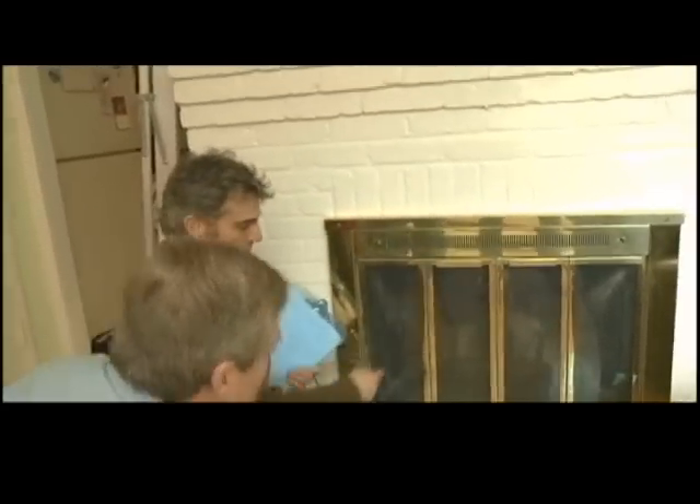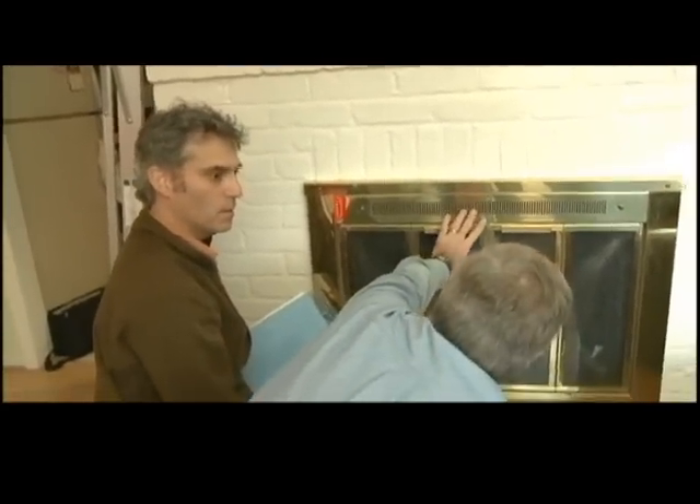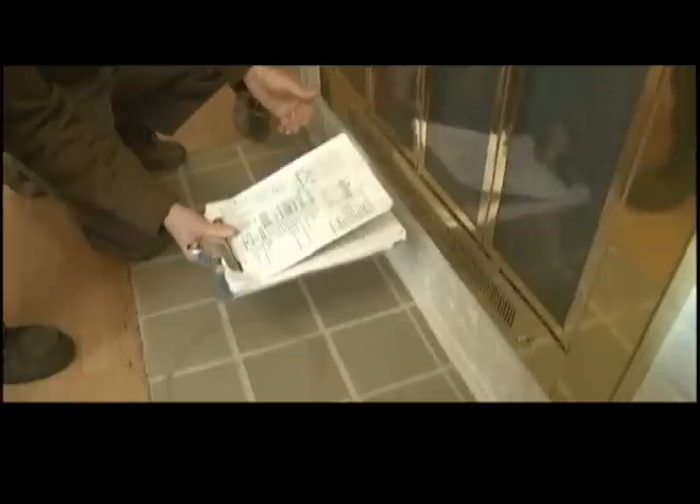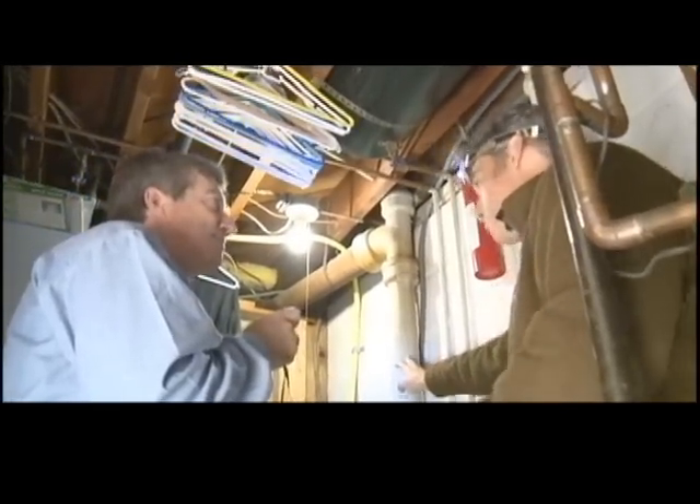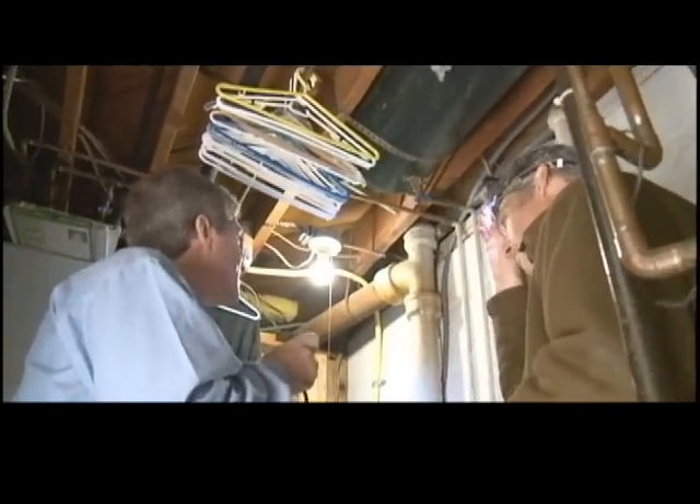And if you feel at the fireplace — put your hand there. Oh yeah, you can really feel a lot of air coming through. And that's with the flue shut. That's right. With the blower door on, we're able to see a lot of leakage down here. You can really feel it, can't you? Oh yeah, feel that air?